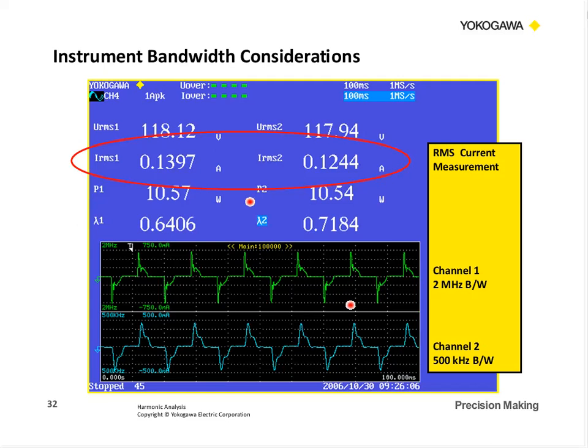When we're dealing with distorted waveforms, instrument bandwidth is a very important consideration. Here's a couple examples. Look at this RMS current right here. Channel 1 had a 2 megahertz bandwidth. You can see the waveform, we can see all the little glitches and everything in it, and the current was measured 0.1397 amps. Over here, the instrument bandwidth was limited to only 500 kilohertz. You can see a lot of those parts are filtered out, smoothed out, and so we're not seeing the same thing. And so our current is measured as 0.1244. There's a difference, and that's due to the bandwidth of the instrument.